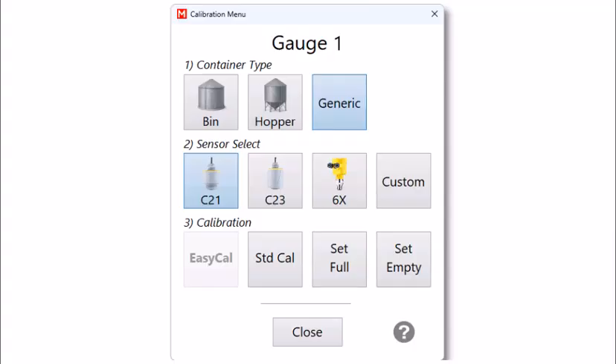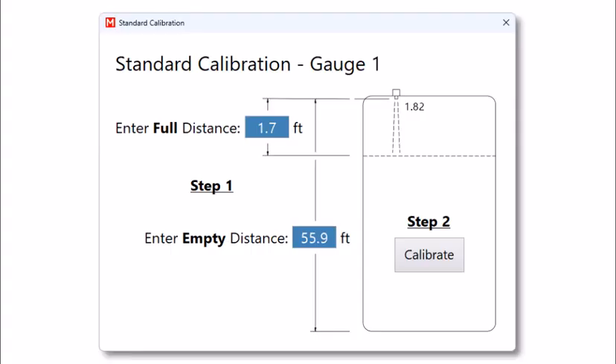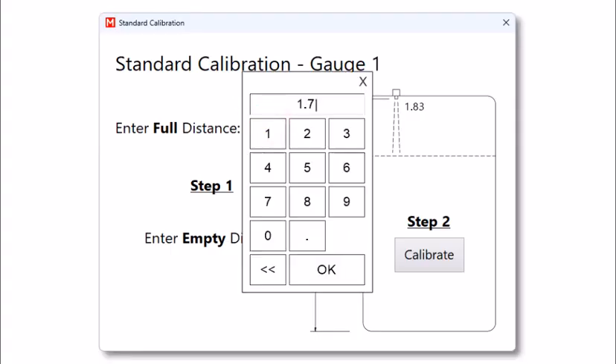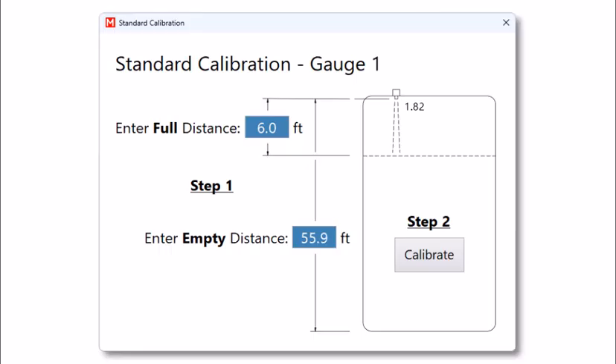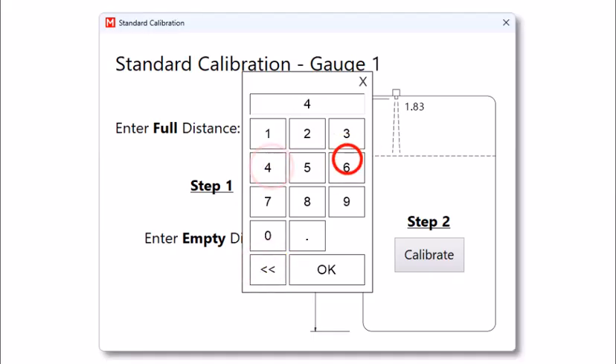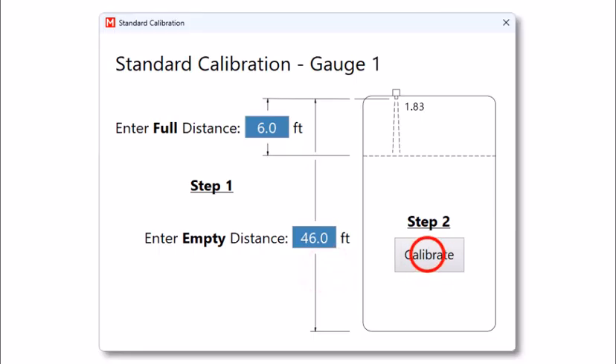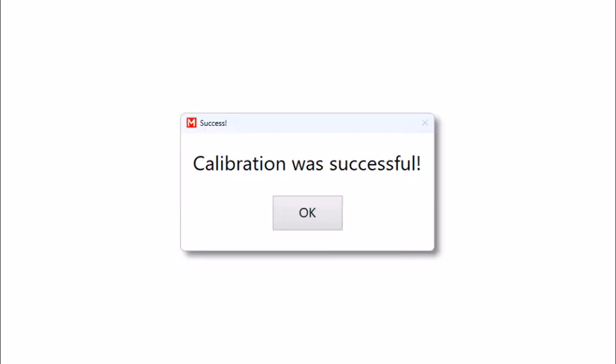Otherwise, if you have a flat top bin, you can follow the remainder of this tutorial section to perform your generic bin's calibration. Set Full and Set Empty retain their functionality. Use these buttons to make minor error adjustments after performing the initial calibration using the standard calibration function. Enter the distance between the sensor and the contents of the bin when the bin is full by clicking on the top blue rectangle labeled Enter Full Distance and using the numeric input pad. Press OK. Next, enter the distance between the sensor and the base of the bin when it's empty. Click the bottom blue rectangle labeled Enter Empty Distance and enter the value. Hit Calibrate and acknowledge the pop-up. Your sensor has now been calibrated.